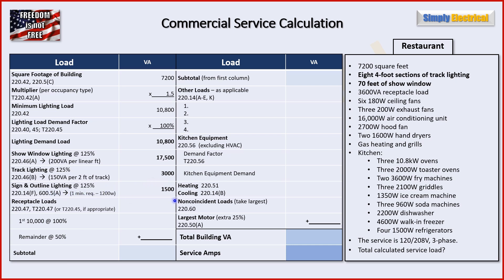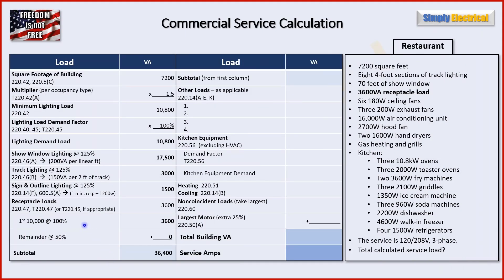For sign and outline lighting, we're not told we have any, but we are required to include at least one in any building with a pedestrian entrance. This being a restaurant, we definitely have one. Per 220.14F, the circuit must be a minimum of 1,200 watts. Times 125% for continuous load, that gives us 1,500 VA. For receptacle loads, we're given a total of 3,600 VA — they gave us the total, so we didn't have to count receptacles individually at 180 VA each.